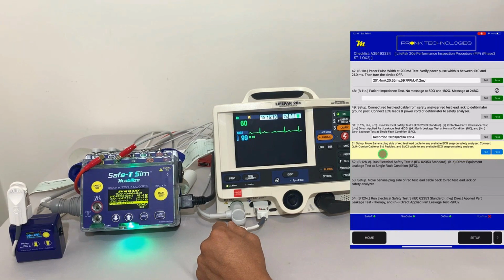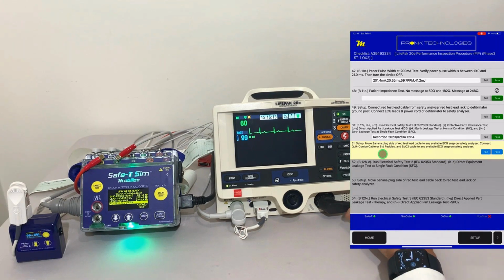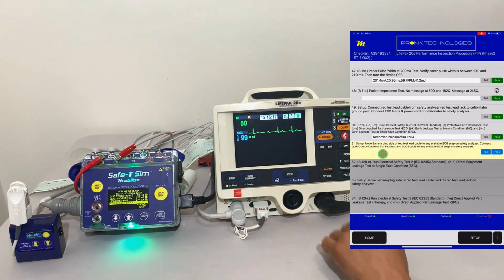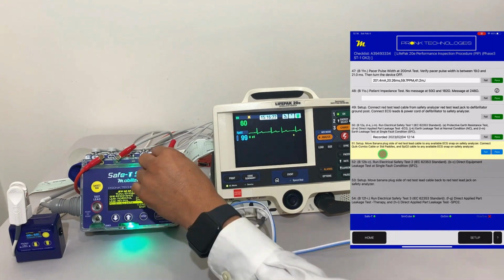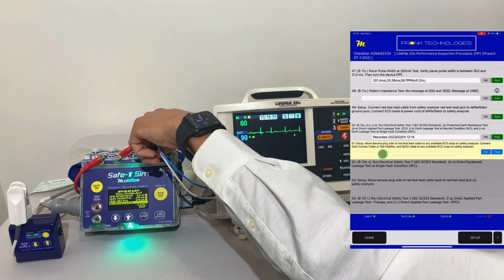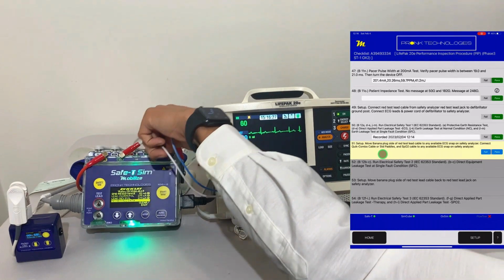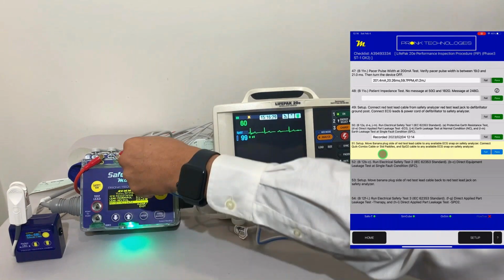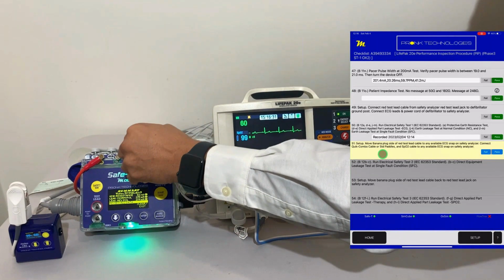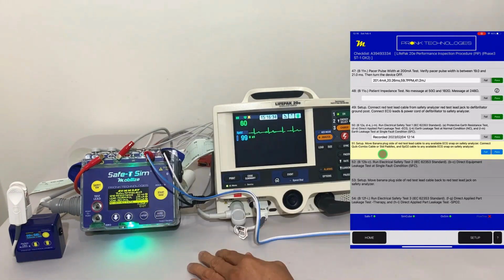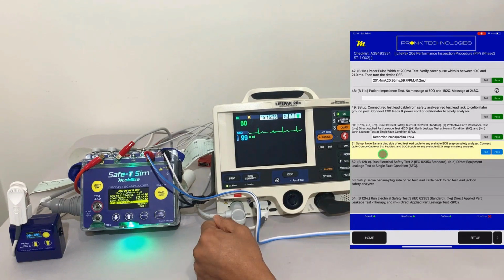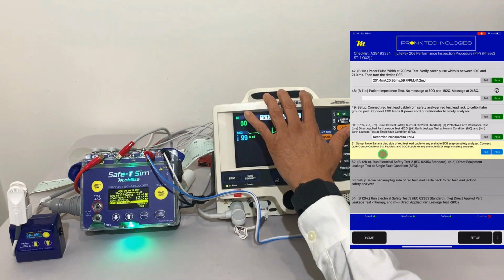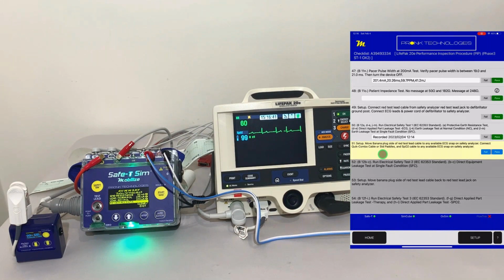And then we also need to connect the quick combo cable because we need to do a leakage test on this as well, because that comes in contact with the patient. Also connect that to the defib analyzer. I'm sorry, to the safety analyzer. So we're going to remove it from the actual defib analyzer, and we're going to connect it over to our safety analyzer. Just slide it underneath one of these plugs like you're seeing here. So now we've secured all of our leads and the device, so we can perform this next test. We've got everything set up properly.